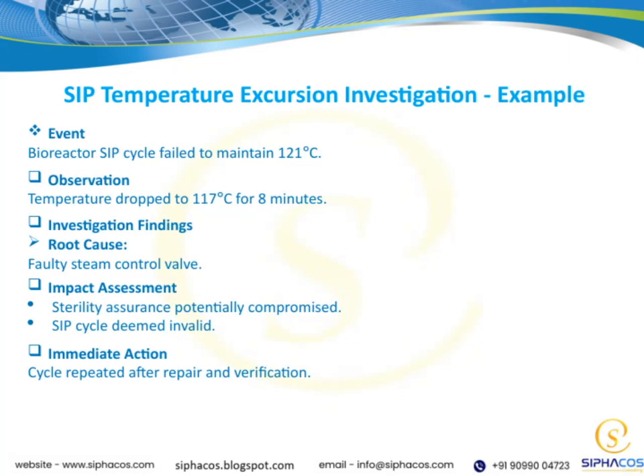Let's look at an example from a SIP temperature excursion investigation. During a bioreactor's sterilization cycle, the temperature didn't hold steady at 121 degrees Celsius as required. Instead, it dropped to 117 degrees for 8 minutes. The root cause? A faulty steam control valve. This meant sterility couldn't be guaranteed, so the cycle was considered invalid. The immediate response was to repair the valve, verify the fix, and then repeat the entire cycle to ensure safety.